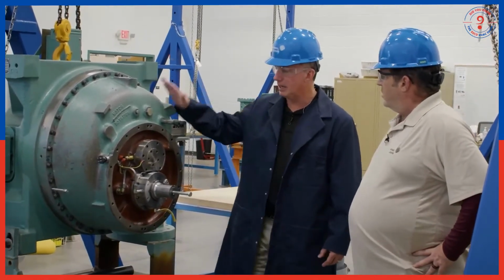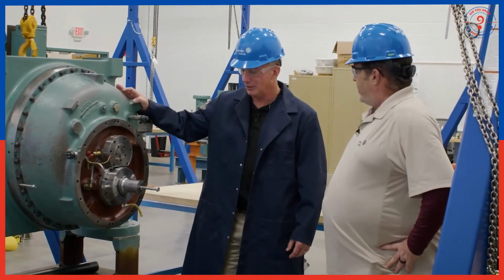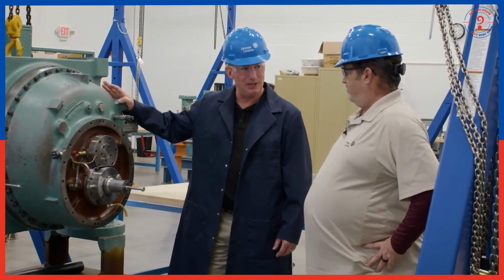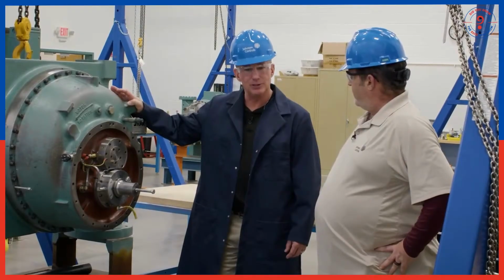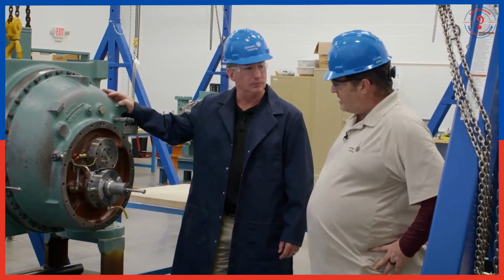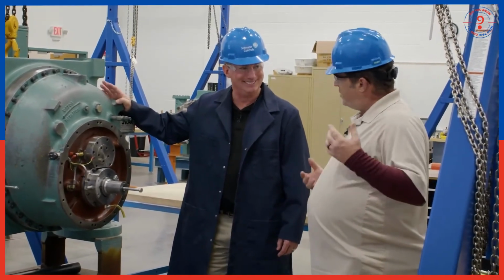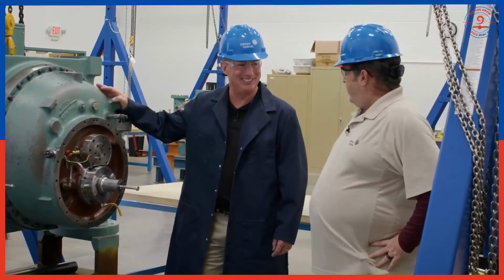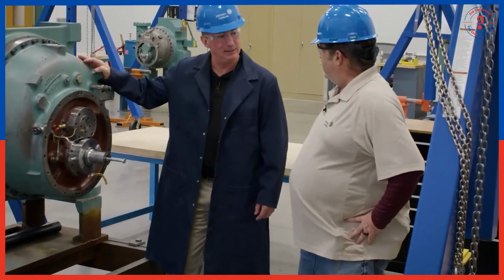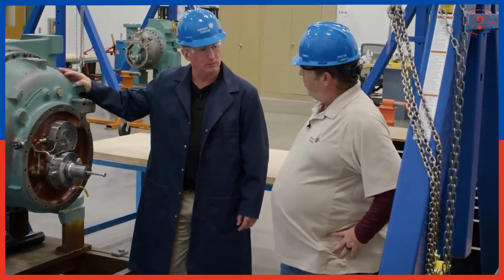So by the time they get done with a fundamental understanding of how they're designed, they're going to tear them apart, inspect, correct, put back together, and so basically the same as doing a full service inspection and rebuild in the field. Yes. Absolutely. It would be exactly like they would do it in the field, except that we have nicer jigs in here, so it does go a little faster. It's a little easier to do in here. It's about a 12-hour process, taking them apart completely, including the PRV and VGD, getting it all back together.